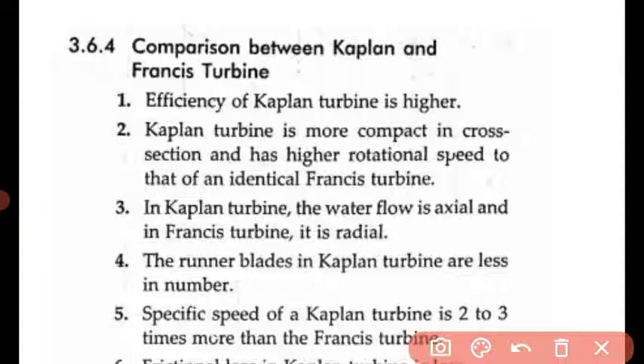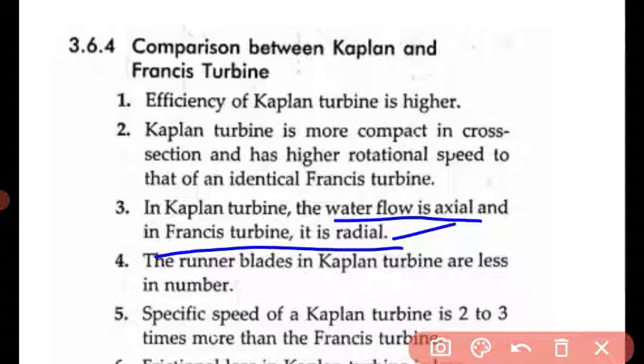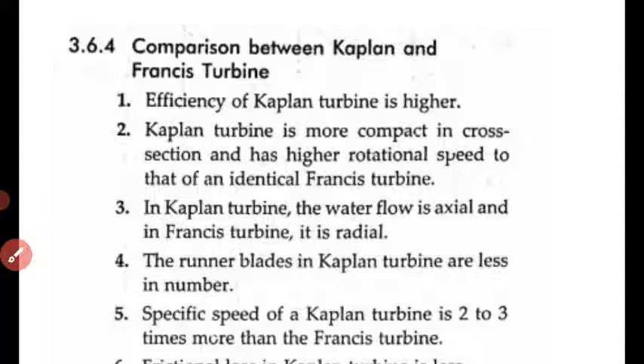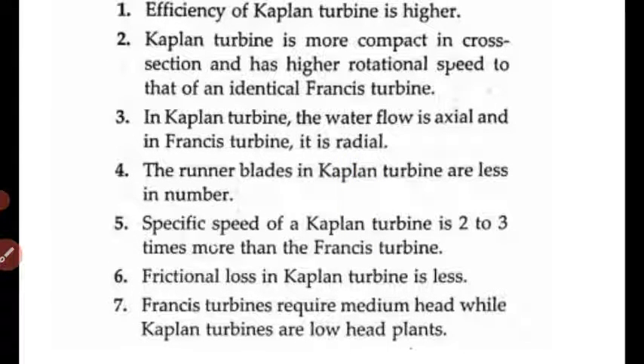An important difference: in the Kaplan turbine the water flow is axial, while in the Francis turbine it is radial. The runner blades in Kaplan turbines are fewer in number. The specific speed of the Kaplan turbine is 2 to 3 times more than the Francis turbine. Friction losses in the Kaplan turbine are less, and Francis turbines require medium head while Kaplan turbines are low-head plants.